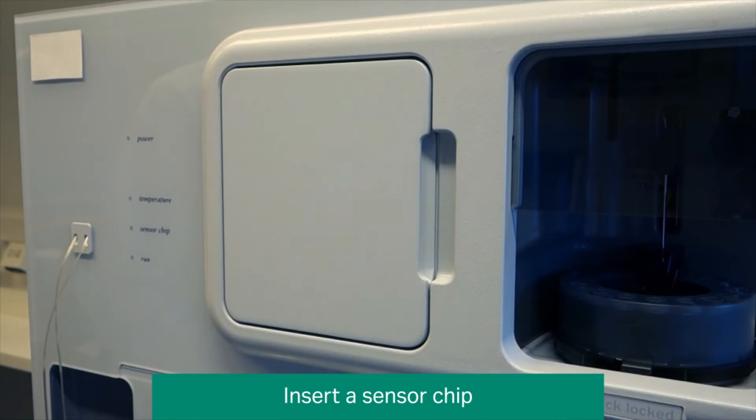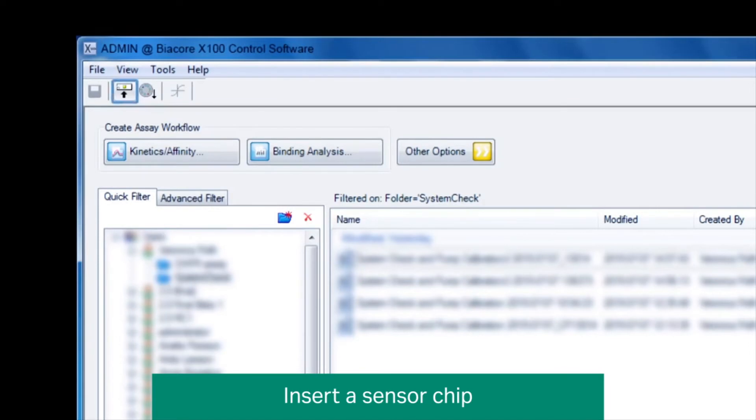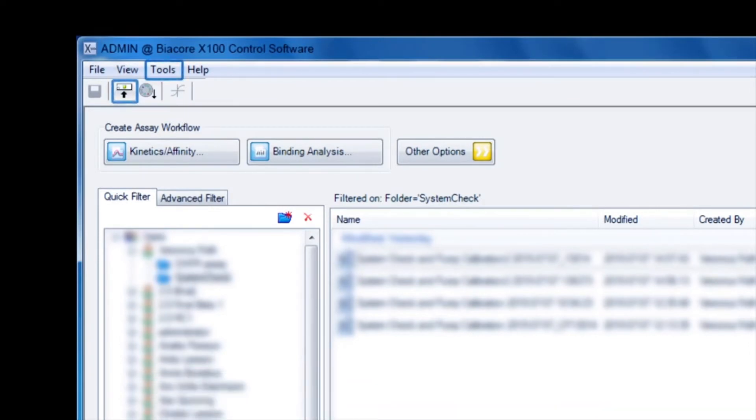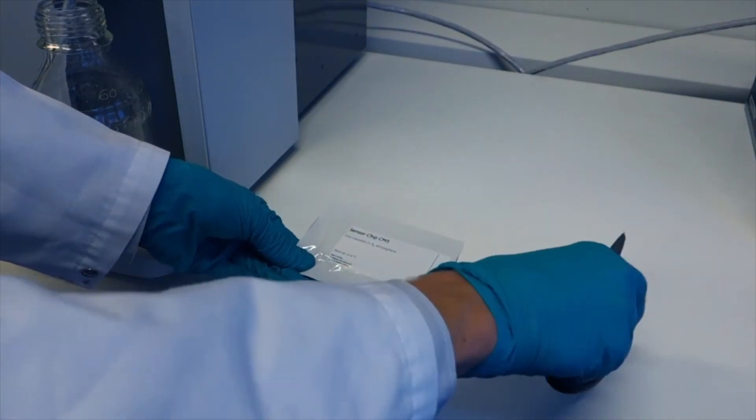To dock a sensor chip, open the front door of the instrument. Click the Undock chip icon or select Undock chip from the Tools menu. Remove the chip from the packaging envelope as follows.